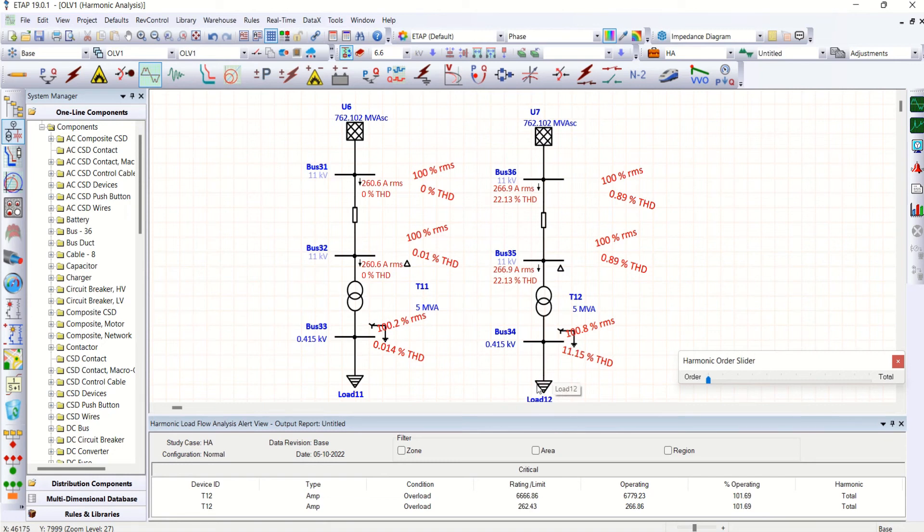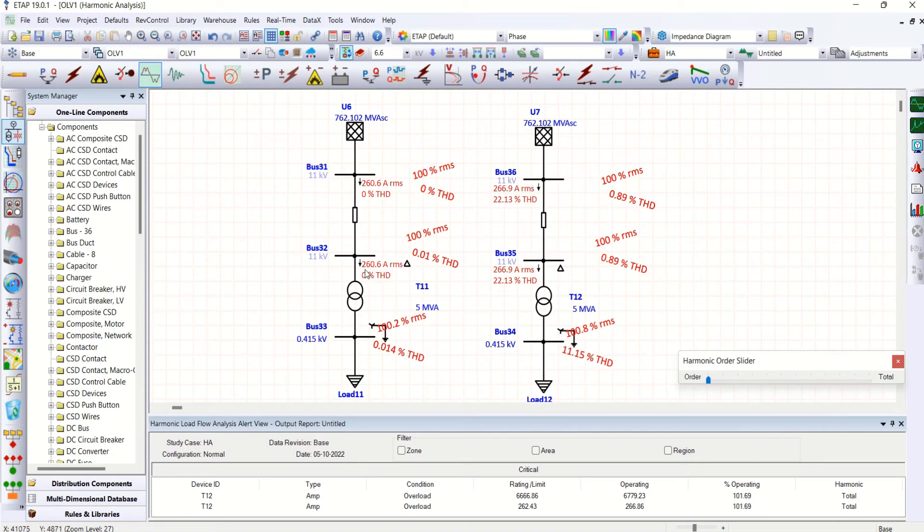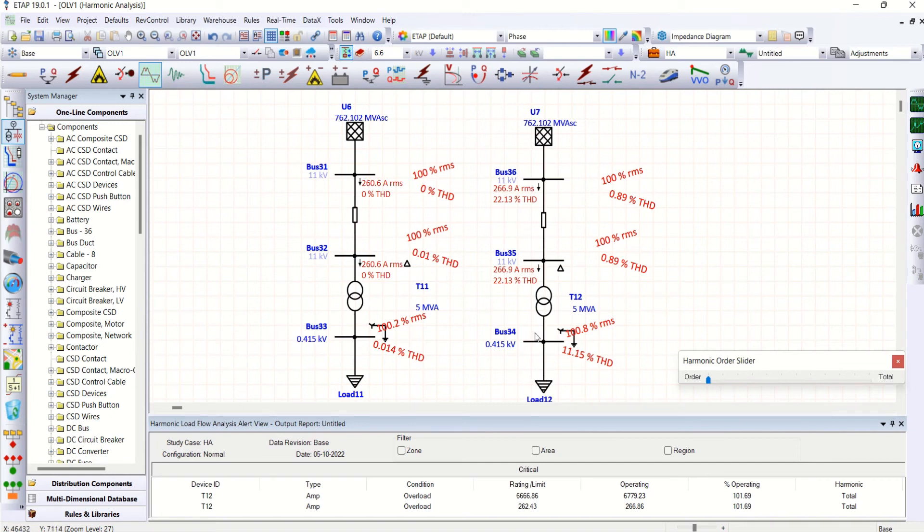Harmonic current injection takes place that increases your total current 260.6 for the non-harmonic load to 266.9 for the harmonic load. Almost 6.3 amps increases here. So this is due to harmonics present in the system.